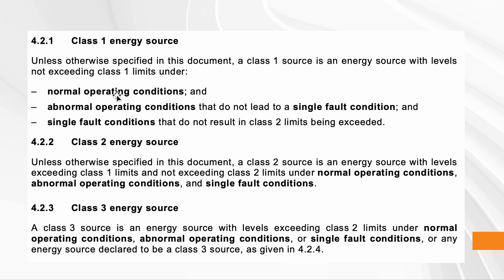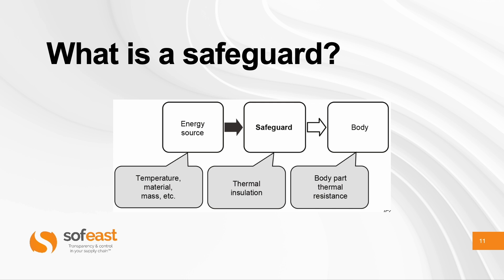You need to think about class levels in terms of the different operating conditions — this is where the concepts start to come together. For example, if there's a Class 1 energy source that under a single fault condition results in going to Class 2, it is actually considered Class 2. Of course, you need to read the standard to fully understand it — I'm just trying to summarize based on my experience.